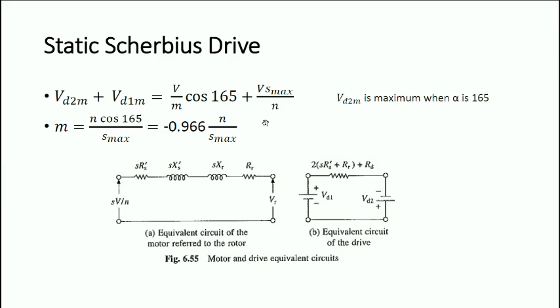Now consider the equivalent circuit of the motor referred to the rotor side, without the magnetizing component. The voltage source is SV/N, and the impedances include the stator resistance and reactance referred to the rotor (S·RS', S·XS'), rotor reactance XR, and rotor resistance RR. This gives us the equivalent circuit of the drive referred to the motor rotor.